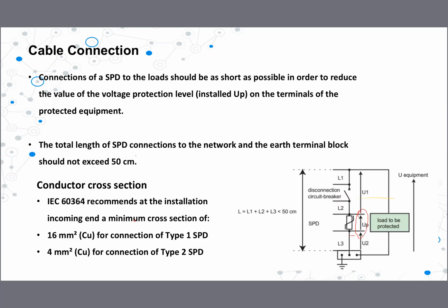UP is the voltage across the terminal. I explained this before. We normally install the surge protection device parallel to the load, right? This is the earth terminal, the load is also connected to the earth, and we install between earth and live conductor, right? So if we use a longer cable, meaning this part and this part, then the required UP doesn't apply across the SPD.